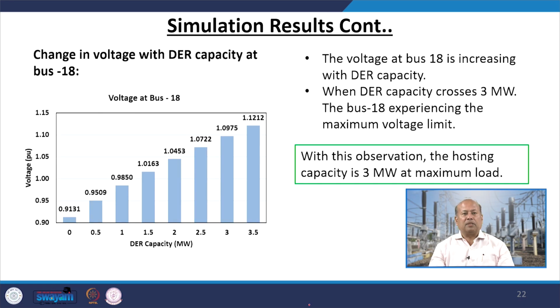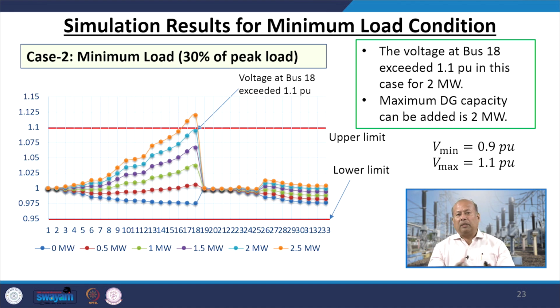We can also see the simulation results, the change in voltage with DER capacity at bus number 18. If you keep on injecting, as you could see, 0, 0.5, 1, 1.5, 2, 2.5, 3, 3.5. The moment you are making 3.5, it is crossing the 10% margin, and hence we have to stop at 3 megawatt penetration at bus number 18. The voltage at bus 18 is increasing with DER capacity. When the DER capacity crosses 3 megawatt, bus 18 experiences a voltage limit violation. So, with this observation, we can say the hosting capacity is 3 megawatt at maximum loading conditions. Now, we can go with minimum load conditions, and we can see similar kinds of scenarios.